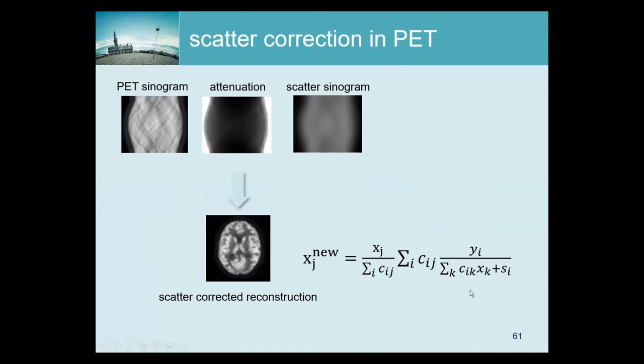Now we can start all over again, because recall this sinogram contains the scatter and our first activity image was wrong because of that. So we can do a better job now. We make an MLEM reconstruction where we account for the scatter — that term goes into the forward projection: we take the image, forward project it, and add the scatter from the scatter sinogram. That should be identical to the measured sinogram. Now this image is going to be an underestimation, but it's going to be better than the previous one.